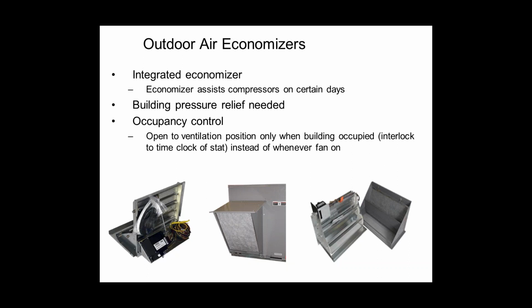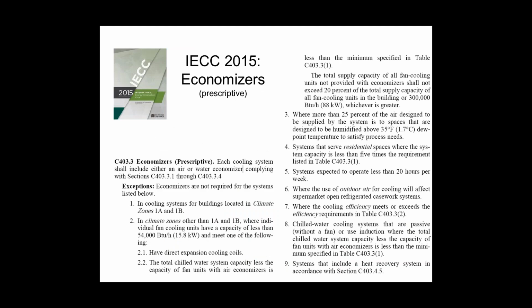And if I can cut back 20 or 30% of your outside air every time the fan turns on all night long, it's a huge energy savings. We've been lobbying for it for years, and it's actually code required now, so it's not even like you have a choice. This will significantly change the thermostat choices you have. It won't really affect the economizer choices because the economizers all can do it. But there's only probably 25 or 30 models of thermostats that do this. So if you need help with that, let me know.